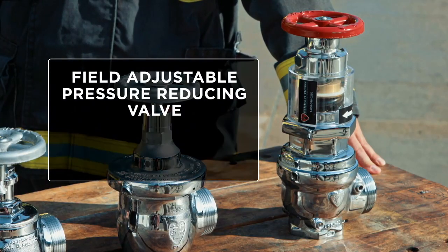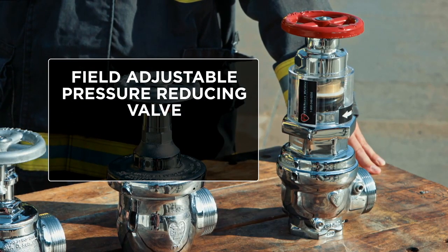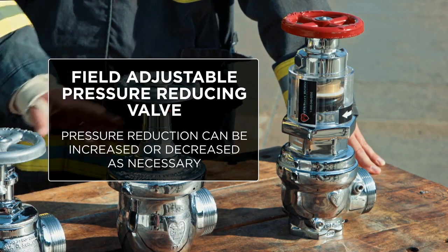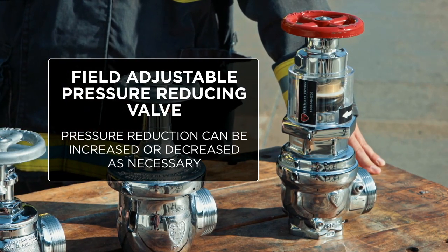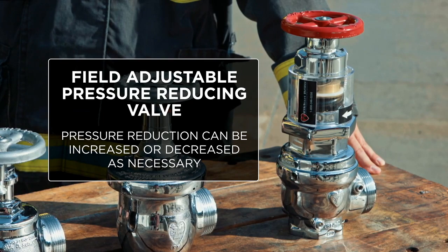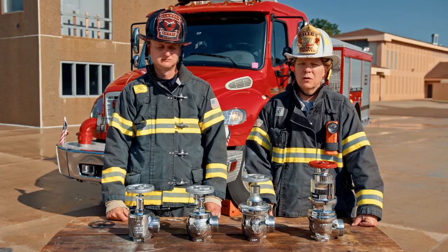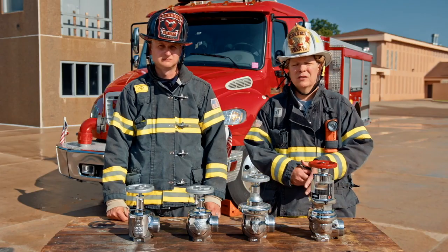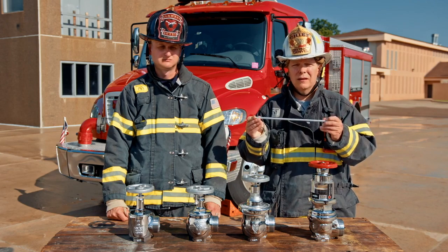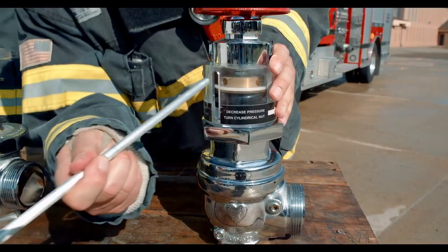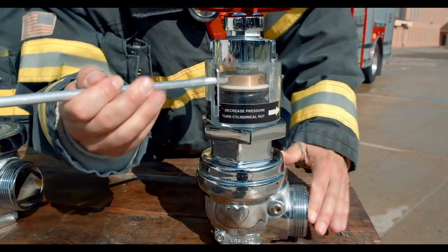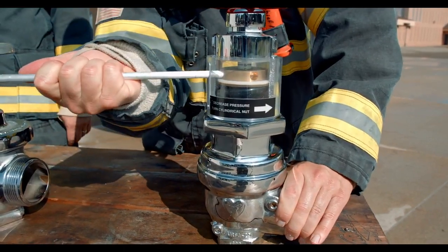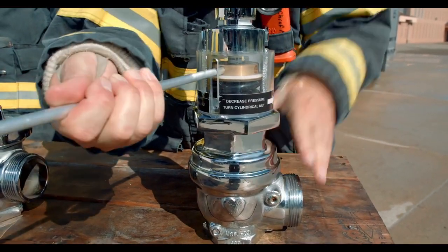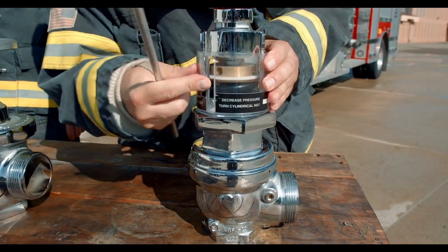The last type of valve is a field adjustable pressure reducing valve. This type of valve would be delivered to the construction site and a pressure set at the time of installation by the installer. This is one of the most user-friendly of those pressure-reducing valves because firefighters can use a valve adjustment rod like this one, 3/8 inch diameter, to insert into the top rotating barrel of this valve and rotating one direction or the other to increase or decrease pressure as necessary.